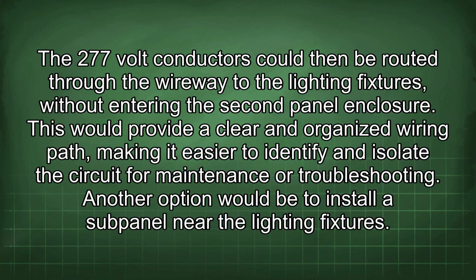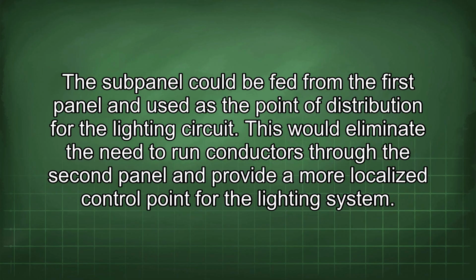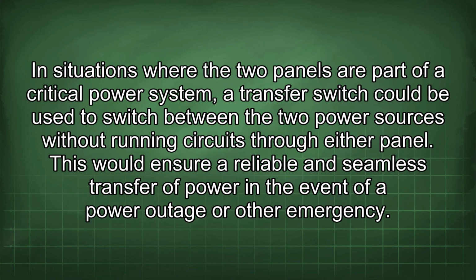This would provide a clear and organized wiring path, making it easier to identify and isolate the circuit for maintenance or troubleshooting. Another option would be to install a subpanel near the lighting fixtures. This subpanel could be fed from the first panel and used as the point of distribution for the lighting circuit. This would eliminate the need to run conductors through the second panel and provide a more localized control point for the lighting system. In situations where the two panels are part of a critical power system, a transfer switch could be used to switch between the two power sources without running circuits through either panel. This would ensure a reliable and seamless transfer of power in the event of a power outage or other emergency.